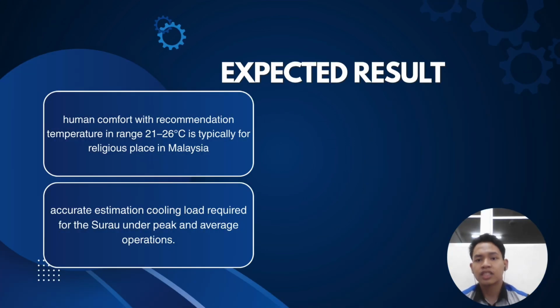What do we expect to achieve by the end of this study? We expect to deliver a highly accurate estimation of the peak and average cooling load required for Surau Al Hadid. This analysis will break down exactly how much of the heat is coming from solar radiation through the building envelope versus internal loads like lighting, appliances, and metabolic heat from human breathing. We will determine the final required capacity in kilowatts or refrigeration tons needed to stabilize the space within the recommended comfort range of 21 Celsius to 26 Celsius.